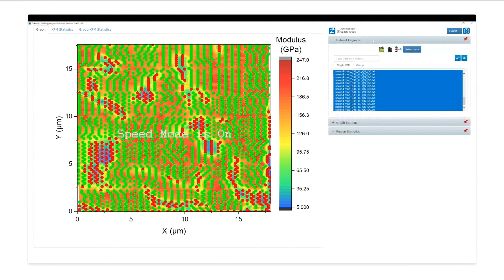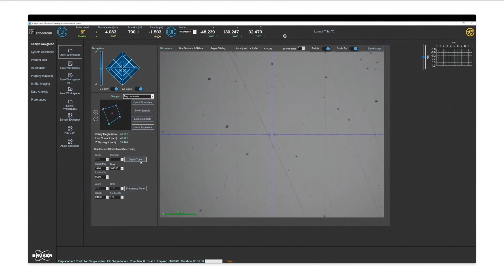In order to automate the AC force setting, we are going to run an indent that tunes the force amplitude using a displacement set point. This measures the stiffness response and sets the correct amplitudes with a feedback routine. So we'll start by selecting the sample and clicking on this depth tune button here.